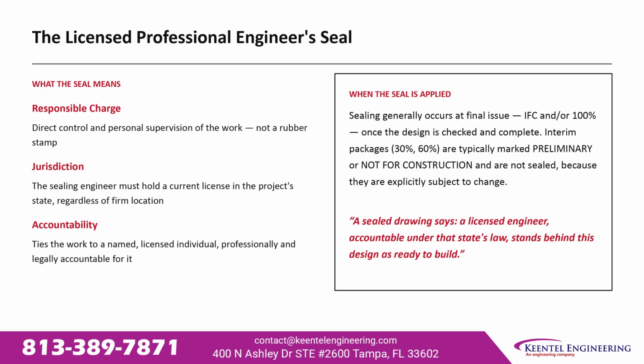The engineer's seal on a substation drawing carries 3 implications. Responsible charge: the sealing engineer exercised direct control and personal supervision of the work. The seal is not a rubber stamp. Jurisdiction: the sealing engineer must hold a current license in the state where the project is located, regardless of where the engineering firm is based.